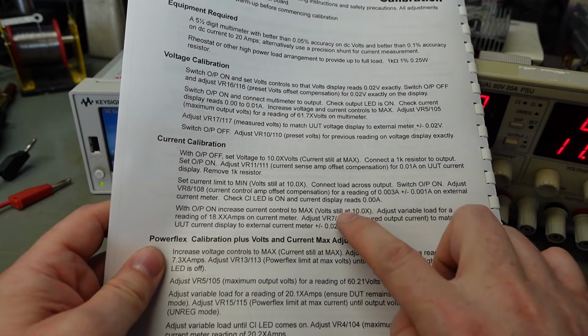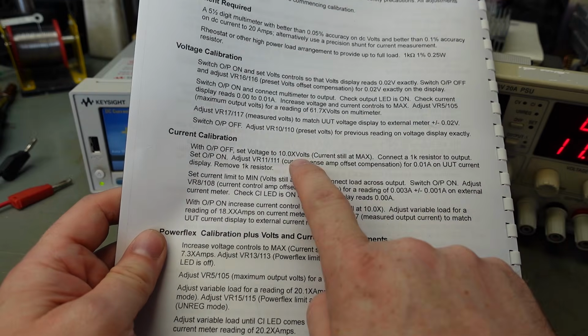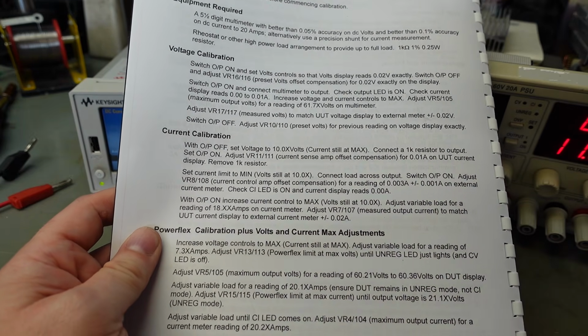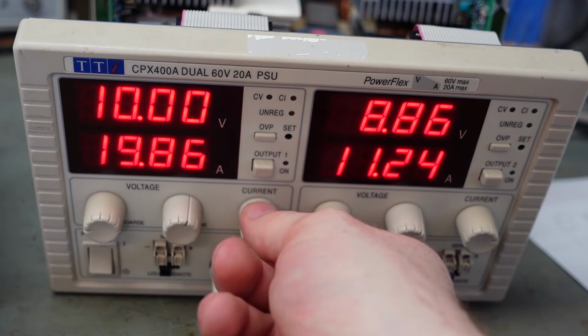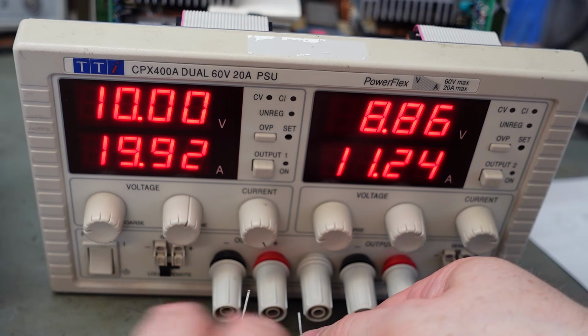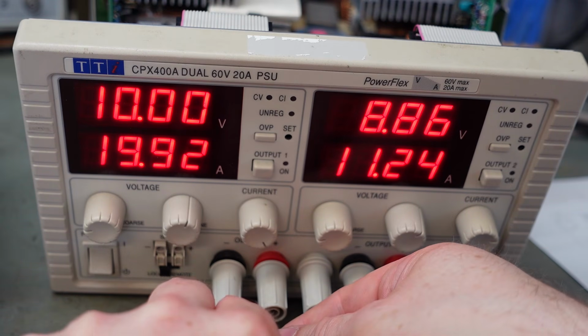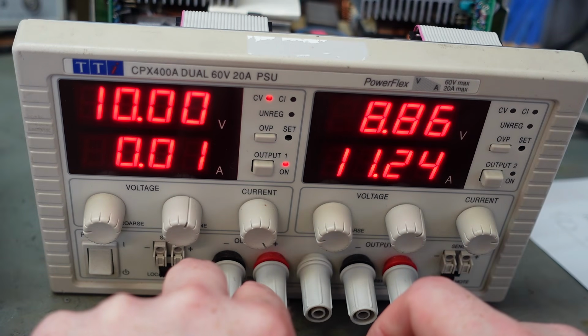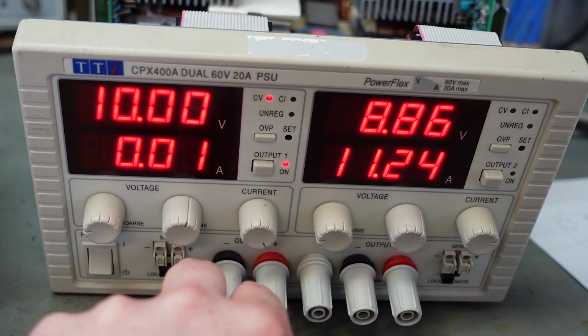Next thing to look at is the current calibration, and the first step is to check that it can read 10 milliamps properly. It tells you to set the current all the way up, oh we're 20 amps, and put a 1k resistor in. It should be 10 milliamps if you turn it on. There we go, no drama there.